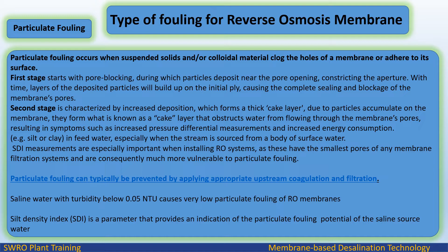The second stage is characterized by increased deposition, which forms a thick cake layer. As particles accumulate on the membrane, they form a cake layer that obstructs water from flowing through the membrane's pores, resulting in symptoms such as increased pressure differential measurements and increased energy consumption.